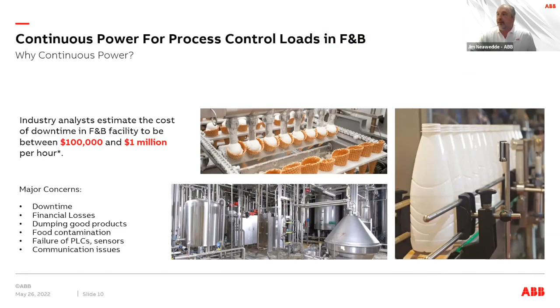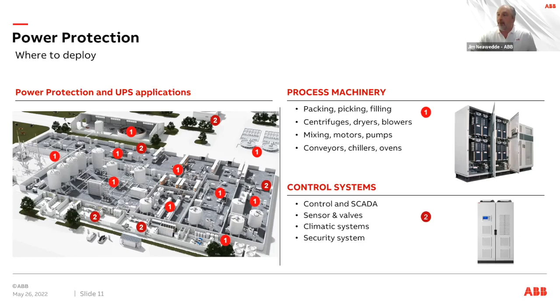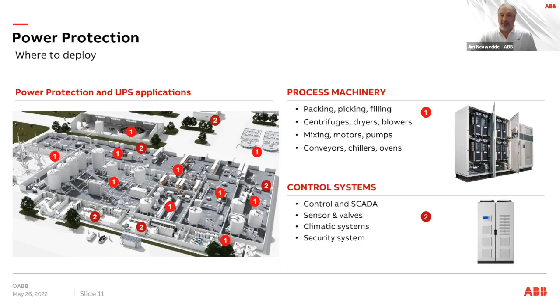So continuous loads for process control are really the issue. And this is applicable for any type of manufacturing. What's important here is that you have the proper power protection. And I also recommend that you include something like a UPS on some of these critical systems. The systems that would be directly affected would be your packing, your picking, your filling, centrifuges, dryers, blowers, mixing operations. Even your control system needs to be protected. If you don't collect data, you're not going to be shipping product. So control systems need to have the proper power protection, and even security systems need to be protected.